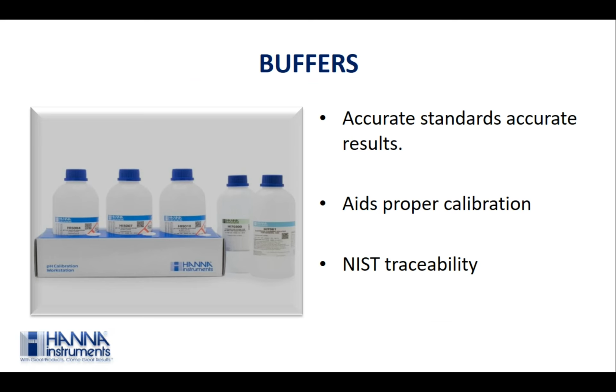And using NIST traceable buffers can give you the surety of the same. These buffers are prepared in standard solution under controlled environment with AR grade chemicals and calibrated A class glassware, thus minimizing the errors in calibration. Also, these NIST traceable buffers have high buffering capacity. Thus, in any case, if a buffer gets contaminated, still the millivolt reading might not exceed the acceptance criteria, thus minimizing the errors in calibration. And these values can be trusted. Using certified buffers having long validity and being stable, thus minimizes the skill needed to prepare in-house buffers.